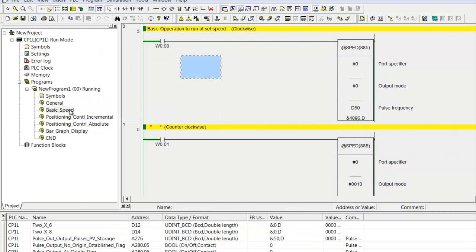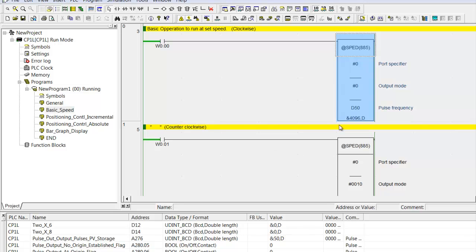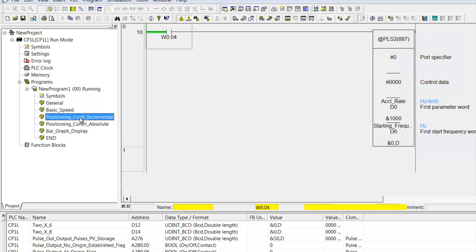For the basic speed control, here's an example of a speed control instruction. This is for jogging. This is for clockwise, counterclockwise. We've got a port specifier for which axis of motion and output mode. Pulse and direction versus clockwise, counterclockwise, and the speed that comes in from the HMI. So clockwise, counterclockwise, jogging.